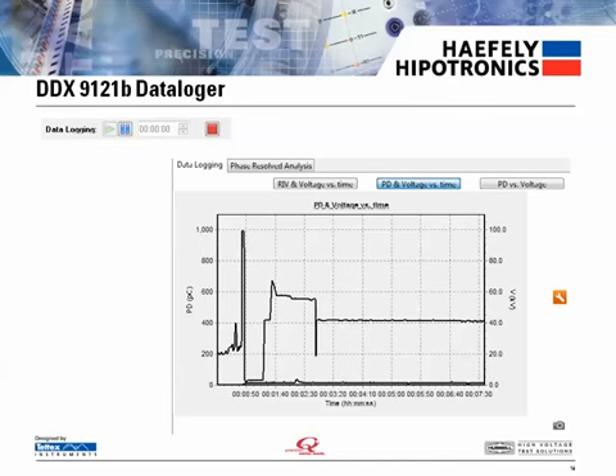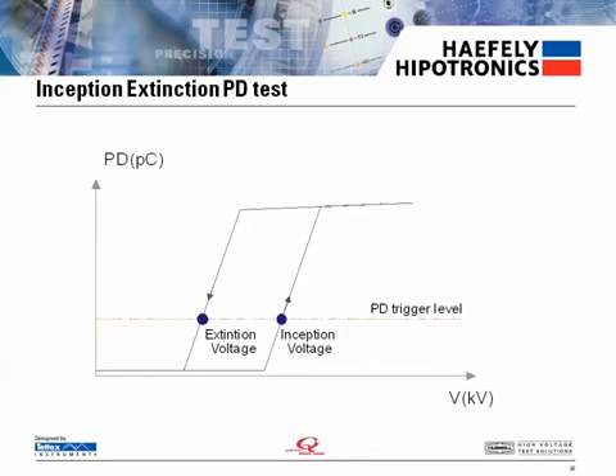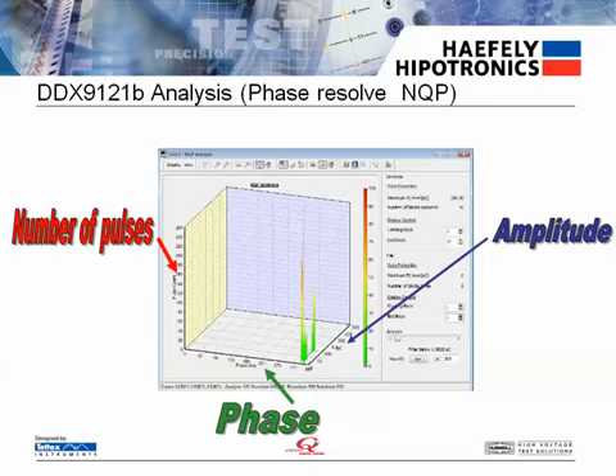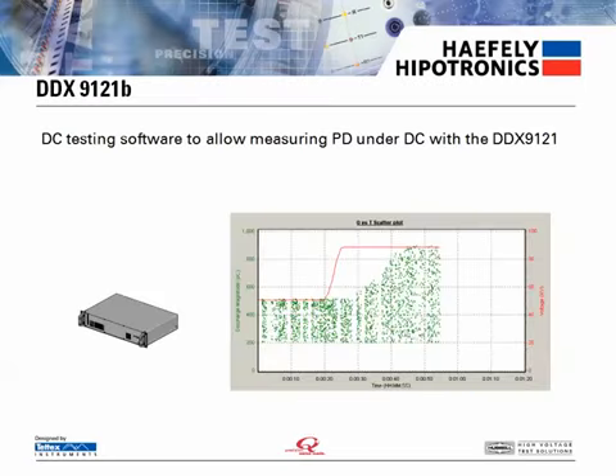The DDX9121B also has a data logger that always keeps track of PD or RIV and voltage versus time, or PD versus voltage. The unit is also capable of performing an inception-extinction PD test where the inception and extinction voltage levels will be saved. Additional analysis capabilities are available with the NQP analysis. And we can also offer an optional software that allows for DC partial discharge measurements.